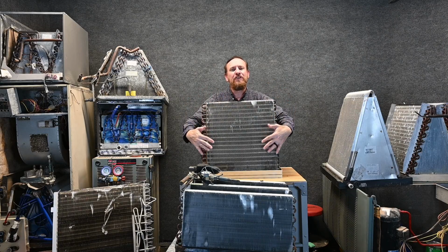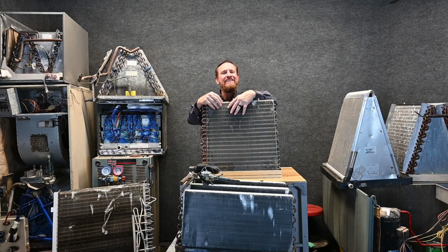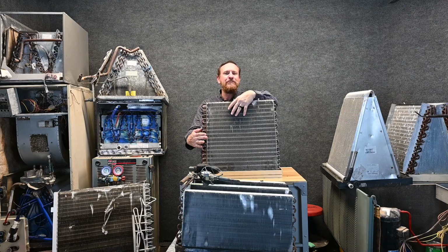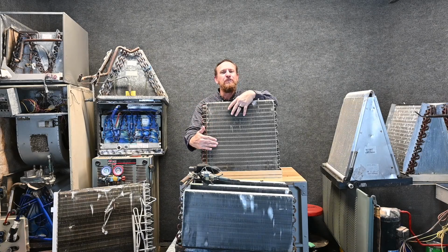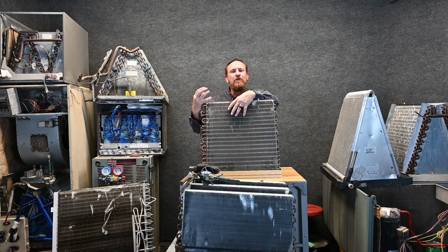As that air comes through this evaporator coil, we want to cool the air enough to where we squeeze the moisture out of the air. Earlier we talked about a dew point temperature, the point at which moisture condenses out of the air. So the refrigerant doesn't only need to be below the air temperature. The refrigerant needs to also be below dew point temperature.